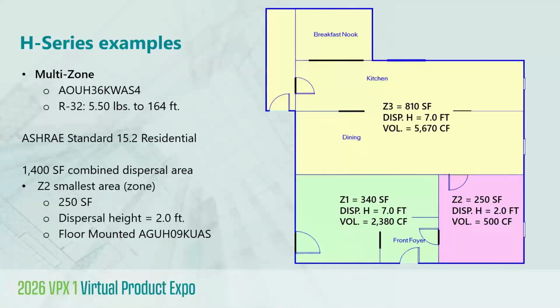So for discussion purposes, let's state that zone 2 that you see there on the lower right has the smallest dispersal volume, which is a function of dispersal area multiplied by the dispersal height. In this case, that you see is only 2 feet. So the first question you might be asking is, why is the dispersal height only 2 feet when, say, we have a ceiling height that could be 8 feet, for example? So the quick answer is because we are going to provide the all-new AGUH floor-mounted unit for this zone, where the lowest point of supply air distribution is actually at the minimum allowed by the standard anyway, which is 2 feet.